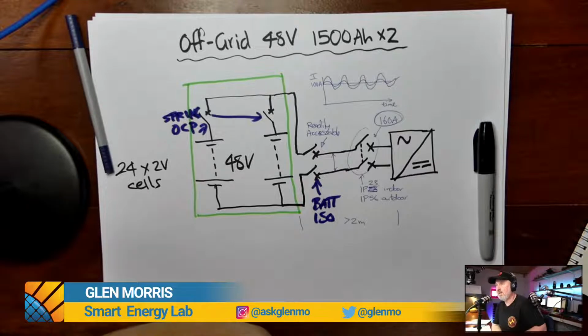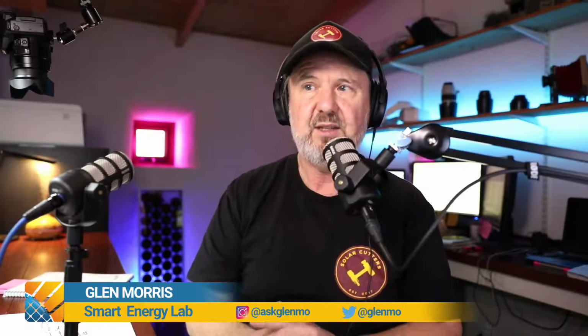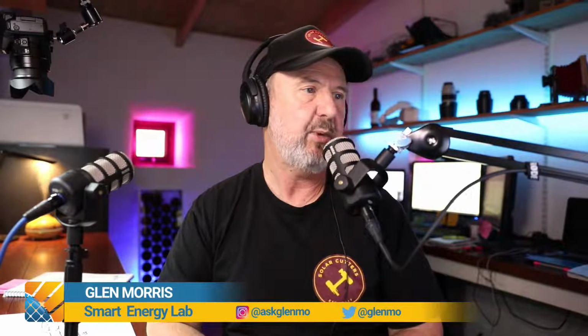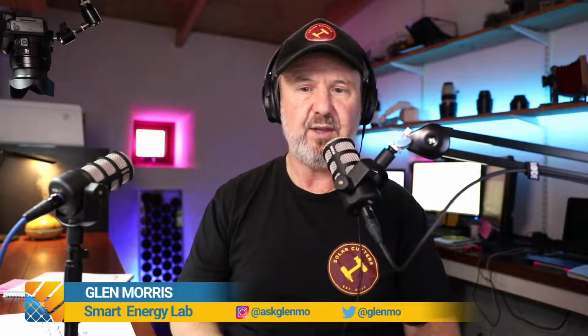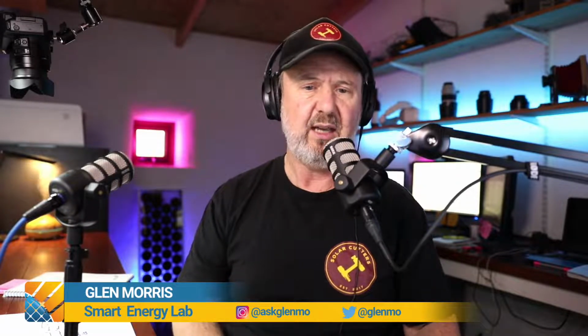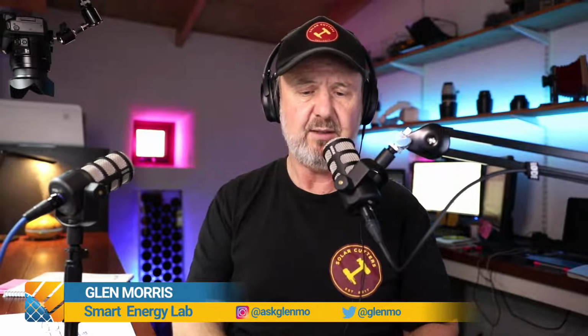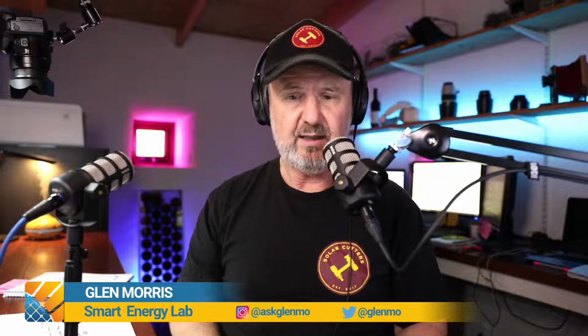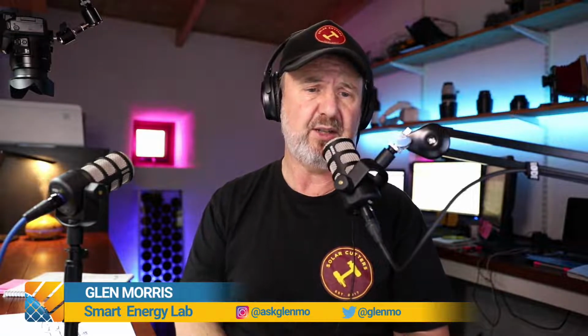Okay, so the next step we're going to do, just cut back, is to look at arc flash and incident energy. Now I talked about this earlier in the week, and I explained that you needed to consider a few things when doing arc flash calculations, and it's a little bit complicated. The formulas are in the standard, but what I've done is produce a little calculator for you that has all the formulas built into it. It's an Excel spreadsheet, and I've just remembered I forgot to put a link to it in the description of my earlier live stream this week, so I'll do it for this one and the earlier one as well. I'm just going to cross over to that now so you can see it.